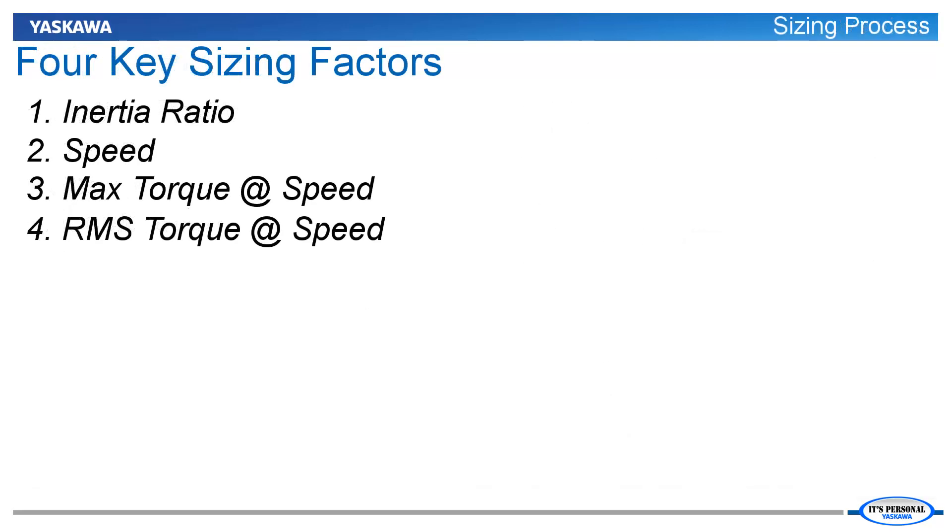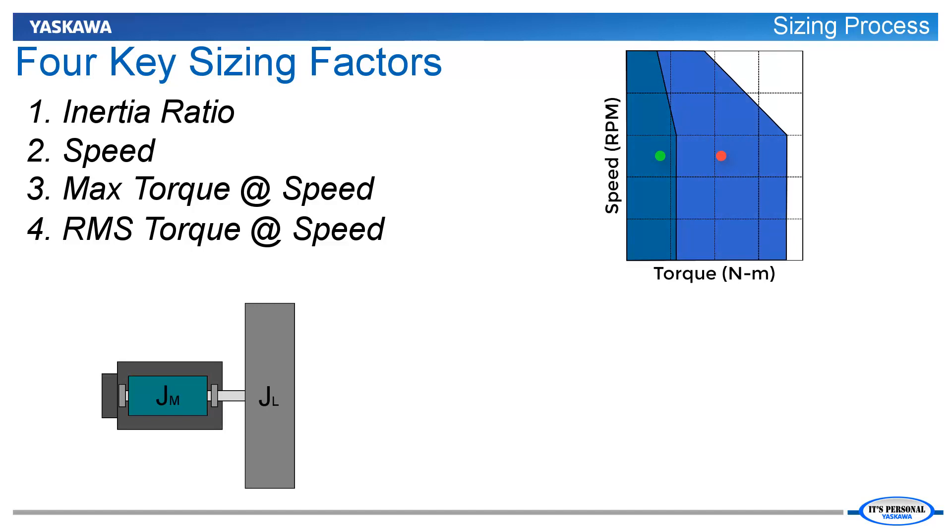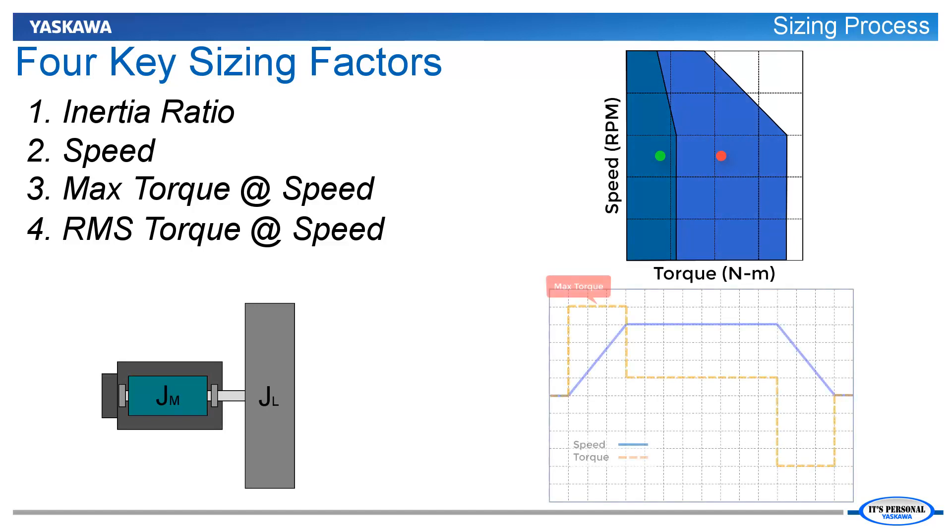While all of these factors are important, the core process in servomotor sizing involves four key factors. Given that the inertia ratio and motor speed are appropriate for the application, both the max torque and the RMS torque must lie within the motor's capability. The remainder of this eLearning module will discuss this process in more detail.